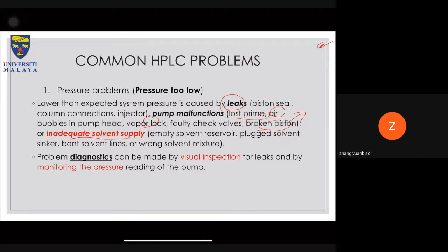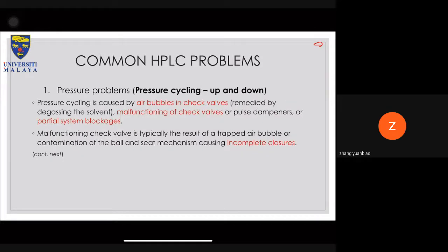Problem diagnosis can be made by visual inspection for leaks or by monitoring the pressure reading of the pump in the system or software. So far, all three main brands of HPLC that I work with, Agilent, Shimadzu, and Waters, all have pressure values in the software. So by just looking at the software, you know whether the pressure is too high or too low.